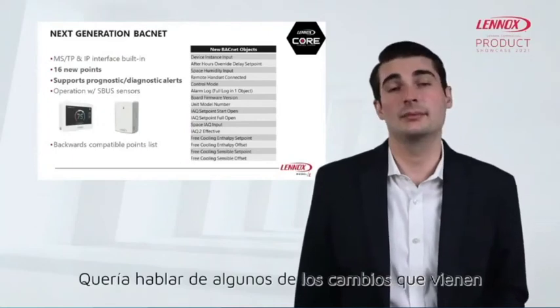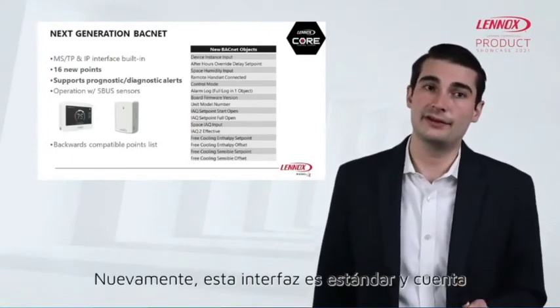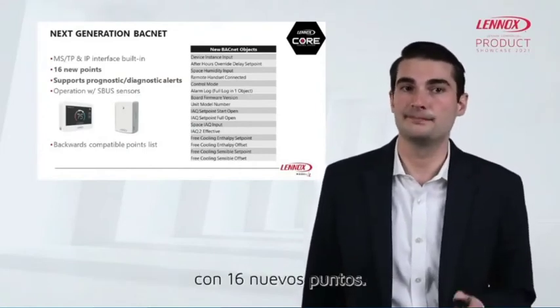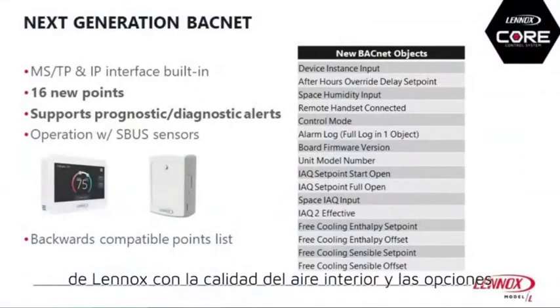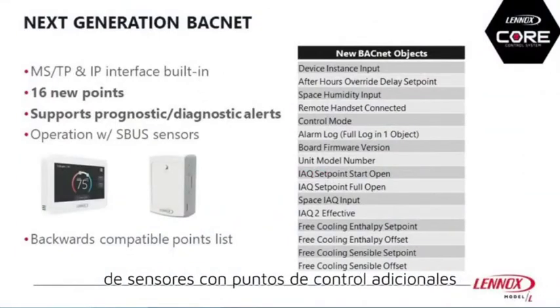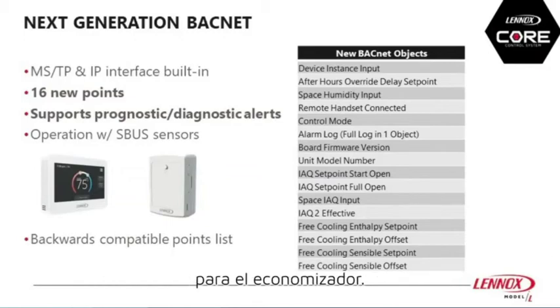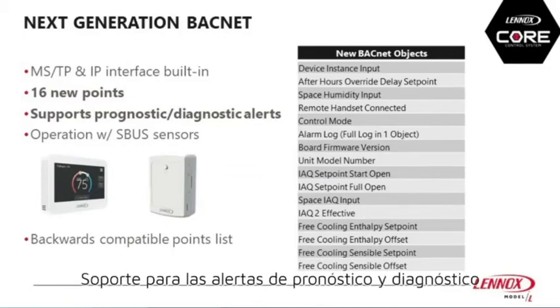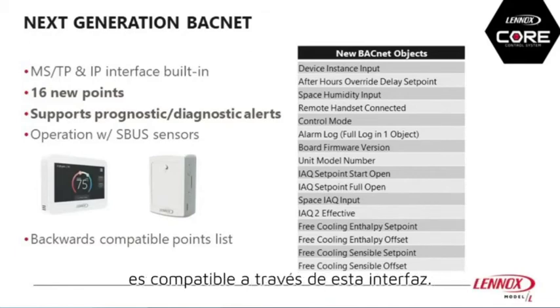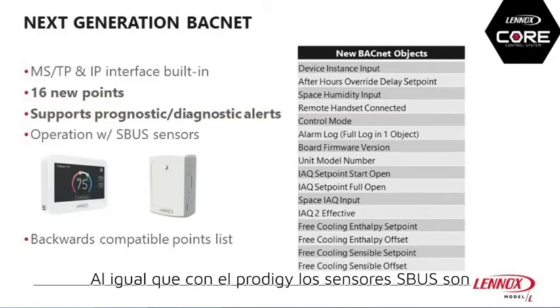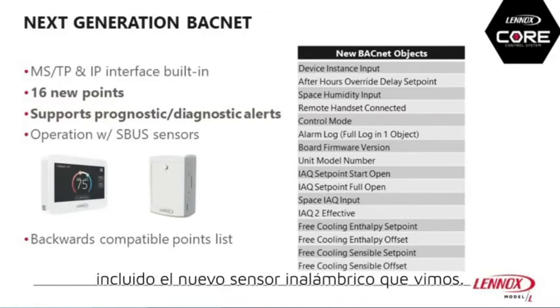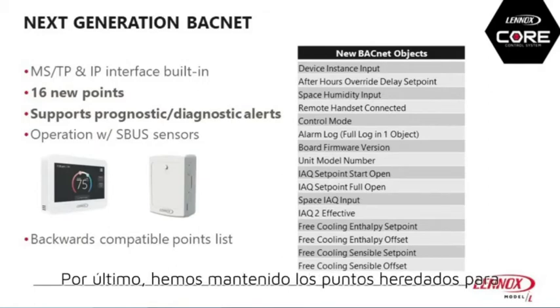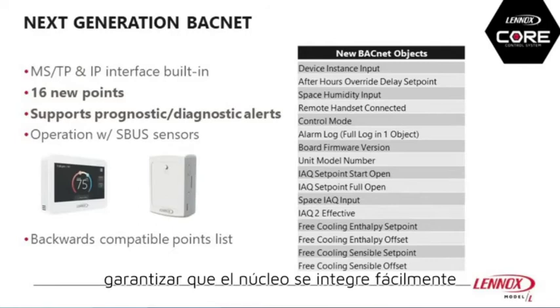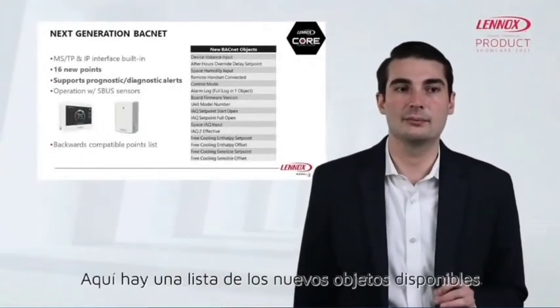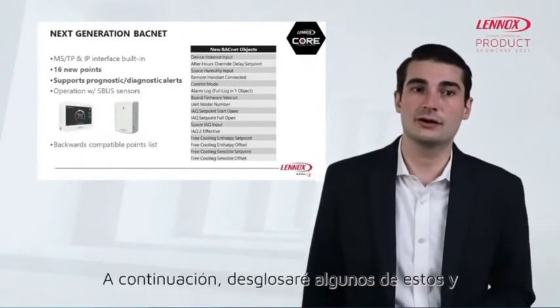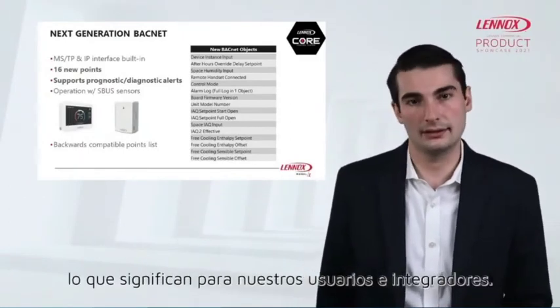Wanted to talk to some of the changes that are coming to our BACnet interface. Again, this interface is standard and features 16 new points. These objects heavily emphasize Lennox's commitment to indoor air quality and sensor options with added control points for the economizer. Support for the prognostic and diagnostic alerts that we will have in this controller is also supported through this interface. As with Prodigy, SBUS sensors are supported for added flexibility within BACnet, including the brand new wireless sensor that you saw. Finally, we have kept legacy points to ensure that CORE easily integrates on replacement jobs. Here is a list of the brand new objects available through BACnet. Next, I'll break down a few of these and what these mean for our users and integrators.